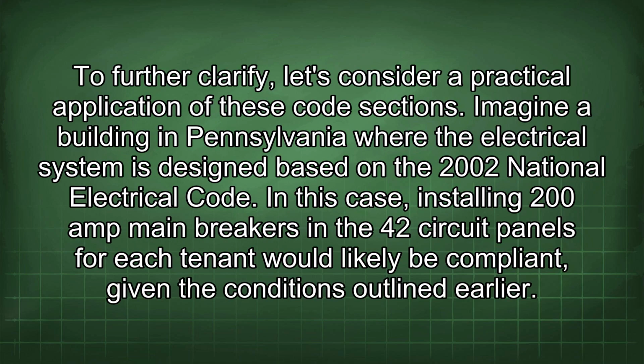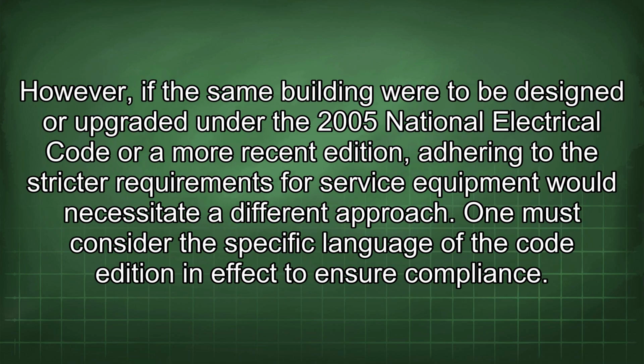To further clarify, let's consider a practical application of these code sections. Imagine a building in Pennsylvania where the electrical system is designed based on the 2002 National Electrical Code. In this case, installing 200 amp main breakers in the 42 circuit panels for each tenant would likely be compliant, given the conditions outlined earlier. However, if the same building were to be designed or upgraded under the 2005 National Electrical Code or a more recent edition, adhering to stricter requirements for service equipment would necessitate a different approach. One must consider the specific language of the code edition in effect to ensure compliance.